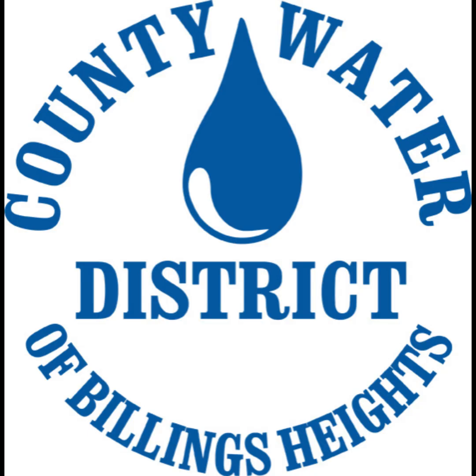The next alternative is installing an elevated tank. The elevated tank would be about 100,000 gallons and it would have a total height of 100 feet. Approximately 1 acre of land would have to be purchased from a private landowner. The exact location of the land is to be determined, since our previous location currently has a church being built on it. Also, as part of the alternative, the Inverness pump station would have to be retrofitted in order to pump the water up to the tank.